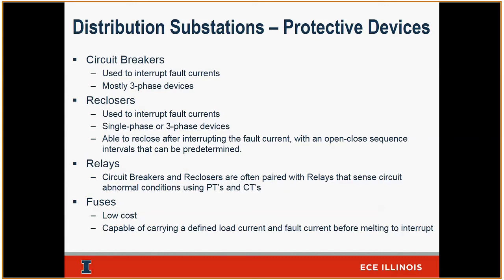Now all of a sudden you have a very small impedance, everything's flowing through that point of connection, and a huge, large spike in current occurs. It could reach up to 4,000 amps. Huge difference between your load current and then your fault current. And that, if it stays, is now causing damage to additional equipment on your system. It could burn lines. It can burn devices. It could cause, again, safety problems.